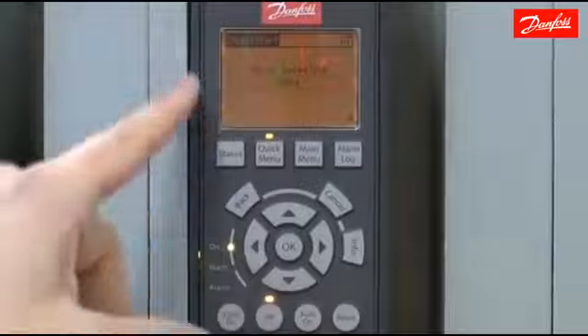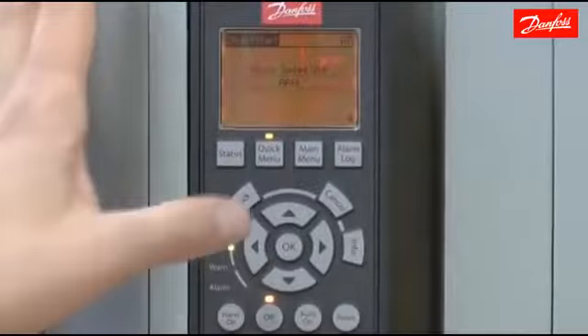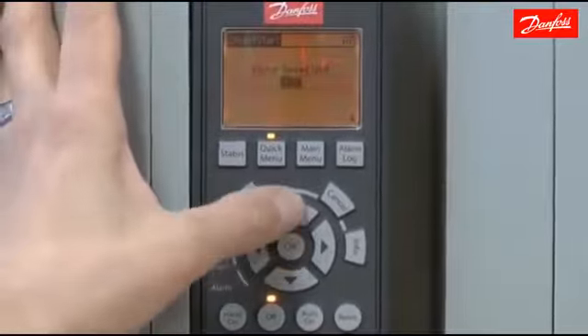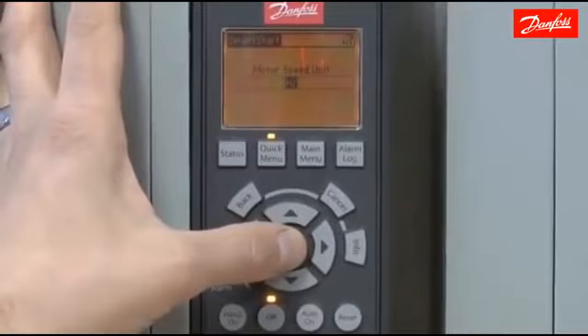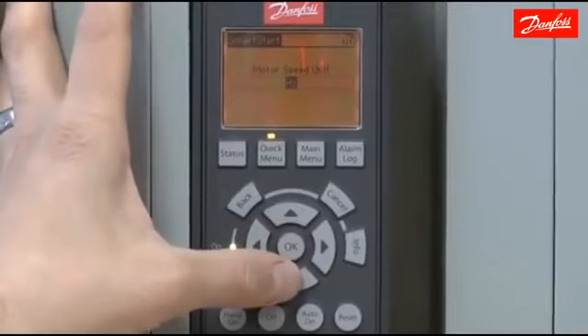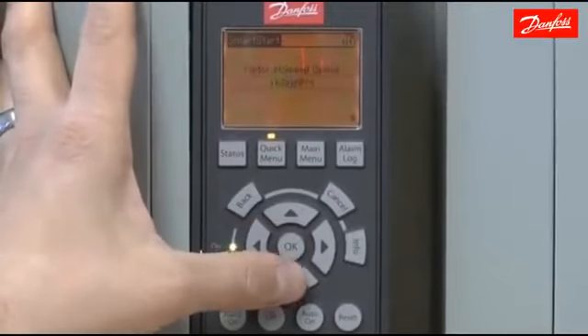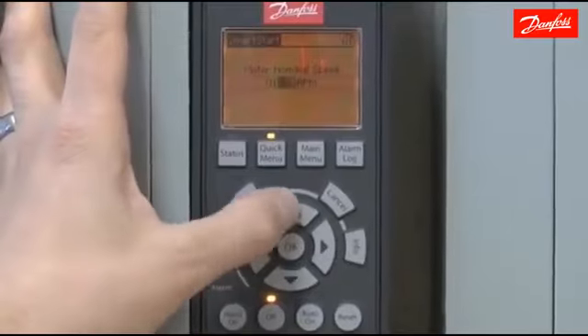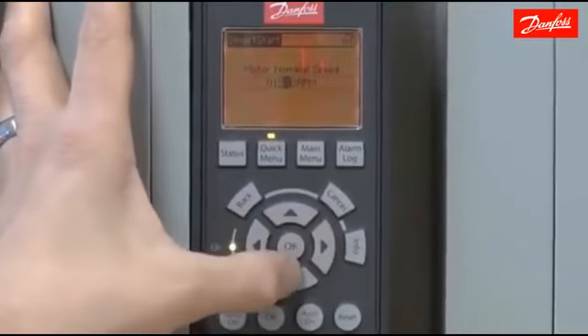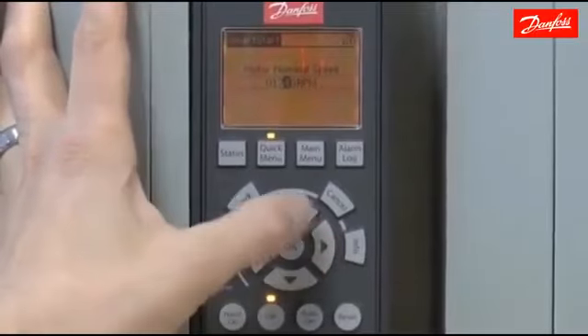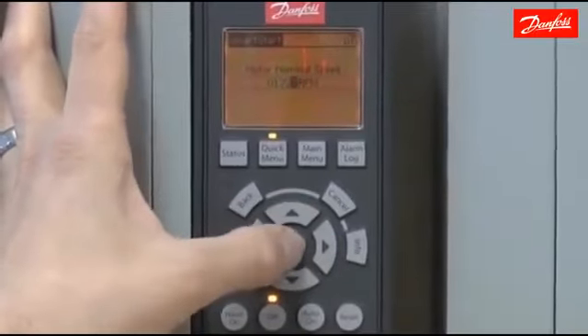The motor speed unit. This is going to ask you what you would like to use for your speed unit. It can be either RPM or Hertz. So when the motor speed is displayed, it'll display in that unit. I'm going to choose Hertz. Motor nominal speed. My motor has a speed of 1735 RPM. That was got right off the motor nameplate.